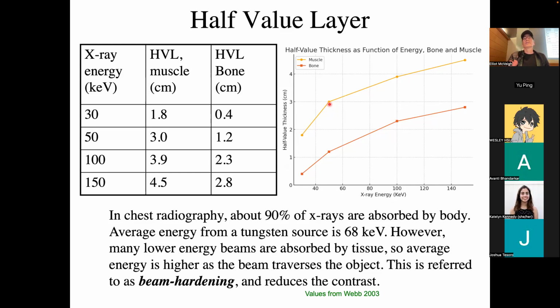Other than that, the patient's overall size is the most important factor when deciding what energy you're going to scan at. As the patient gets bigger and bigger, you usually scan at higher and higher energies such that more photons get through.